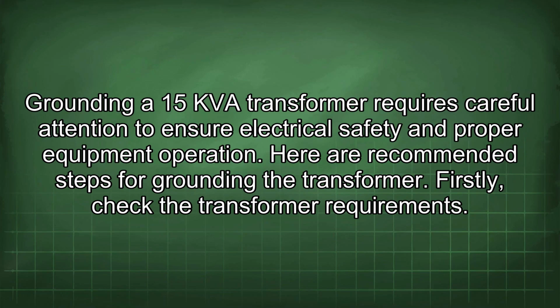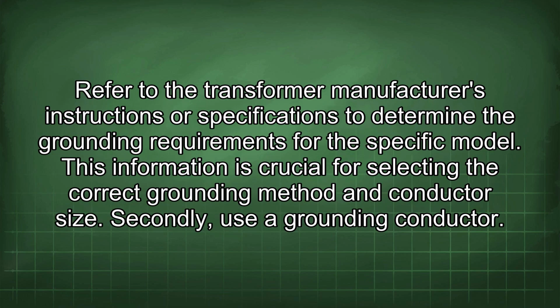Grounding a 15 kVA transformer requires careful attention to ensure electrical safety and proper equipment operation. Here are recommended steps for grounding the transformer. Firstly, check the transformer requirements. Refer to the transformer manufacturer's instructions or specifications to determine the grounding requirements for the specific model. This information is crucial for selecting the correct grounding method and conductor size.